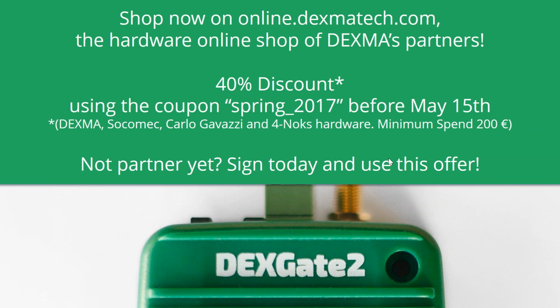What about how many Modbus addresses can be configured in the Dexgate? In fact, Modbus is limited in the same bus to 247 devices. You cannot set more than 247 different addresses in the same bus. That's the theoretical limit. But as you know, you can have remote bridges with 247 more addresses.